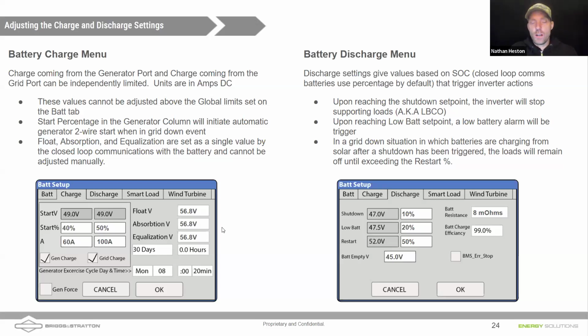On the battery discharge side, the next tab, what values do you see on the screen? You see a shutdown, a low battery, and a restart. Now I note here that you can see that volts are grayed out. That's because the battery we selected to use uses battery percentage. So if you have the battery percentage box checked, you would always see that battery voltage grayed out, and vice versa. If you had a different battery that was non-communicating, you might see the percentages grayed out and the volts as your settable values there. Ours automatically sets percentage. The shutdown percent is when the inverter will stop supporting loads from battery.